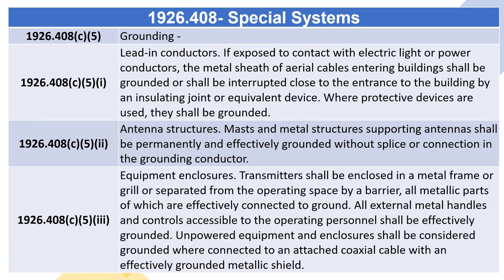1926.408(C)(5) — Grounding. 1926.408(C)(5)(i) — Lead-in Conductors. If exposed to contact with electric light or power conductors, the metal sheath of aerial cables entering buildings shall be grounded or shall be interrupted close to the entrance to the building by an insulating joint or equivalent device. Where protective devices are used, they shall be grounded. 1926.408(C)(5)(ii) — Antenna Structures. Masts and metal structures supporting antennas shall be permanently and effectively grounded without splice or connection in the grounding conductor. 1926.408(C)(5)(iii) — Equipment Enclosures. Transmitters shall be enclosed in a metal frame or grill, or separated from the operating space by a barrier, all metallic parts of which are effectively connected to ground. All external metal handles and controls accessible to the operating personnel shall be effectively grounded.